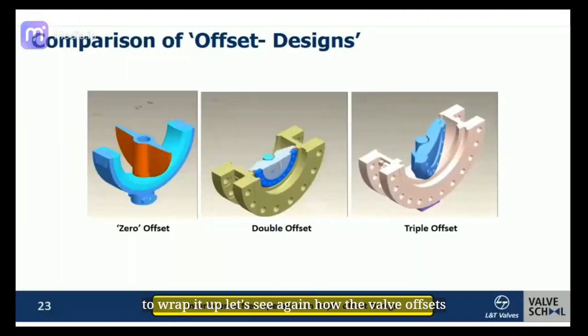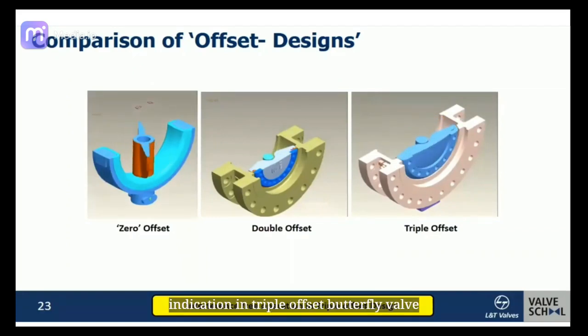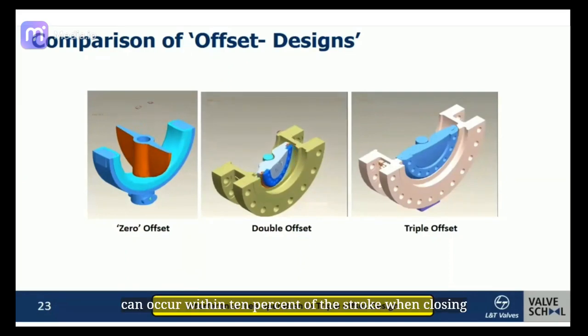To wrap it up, let's see again how the valve offset prevents rubbing between disc and seat. As you see, there is not any rubbing indication in triple offset butterfly valve and the contact of disc and seat is only at the end of the stroke. However, for concentric butterfly valve, rubbing can occur within 10% of the stroke when closing. It is much less in double offset type but still there for the last 2 to 3 degrees.